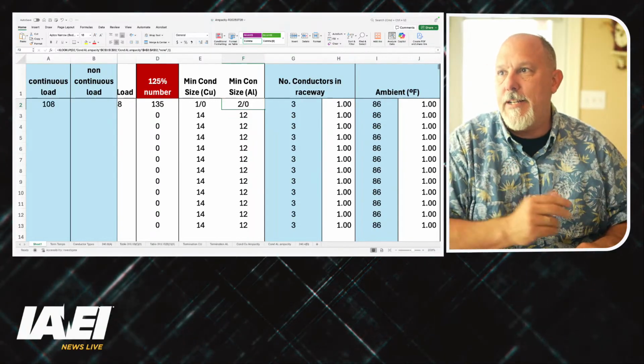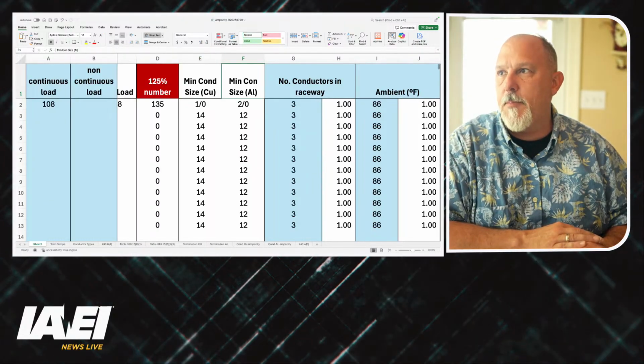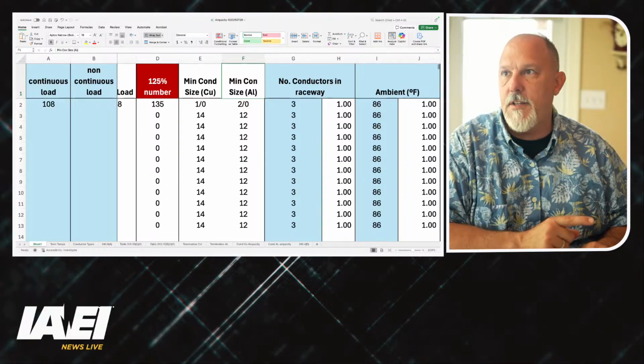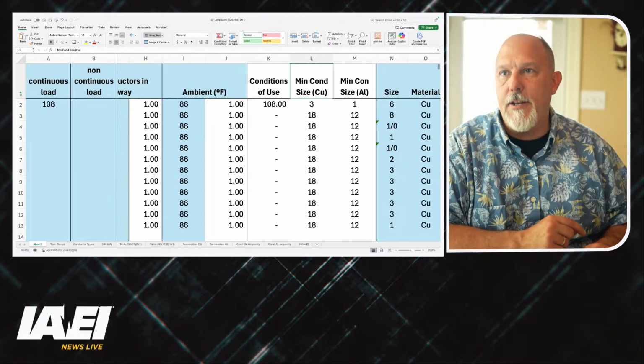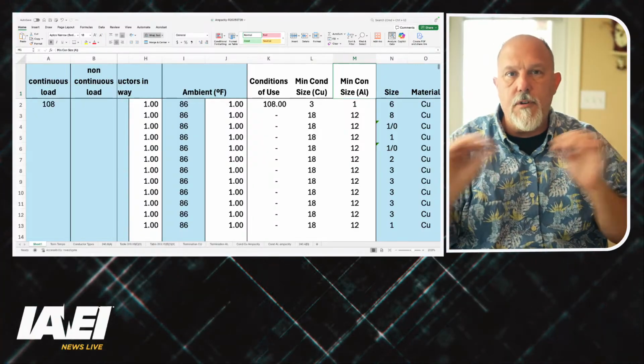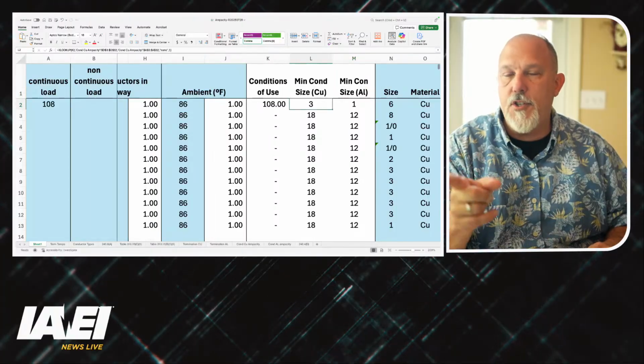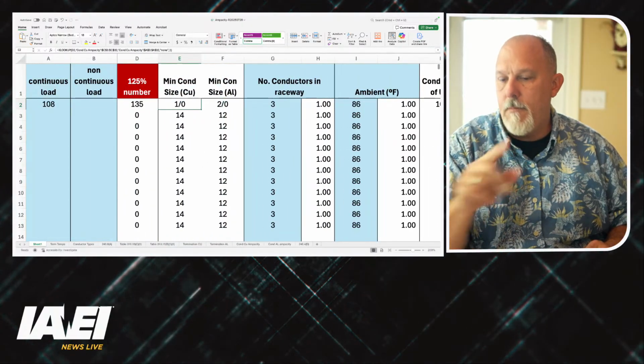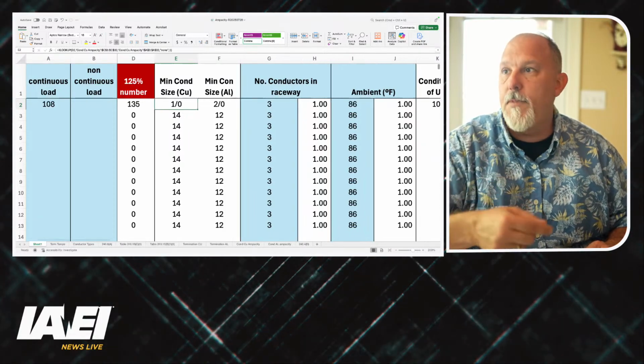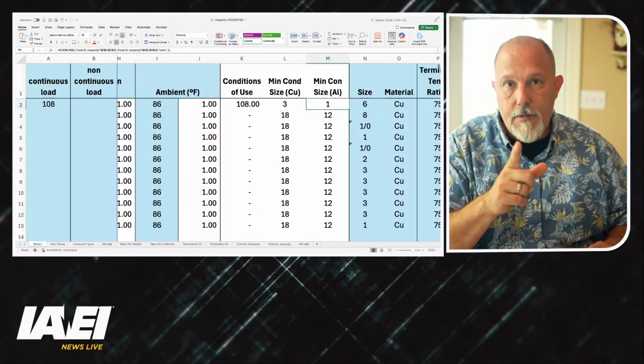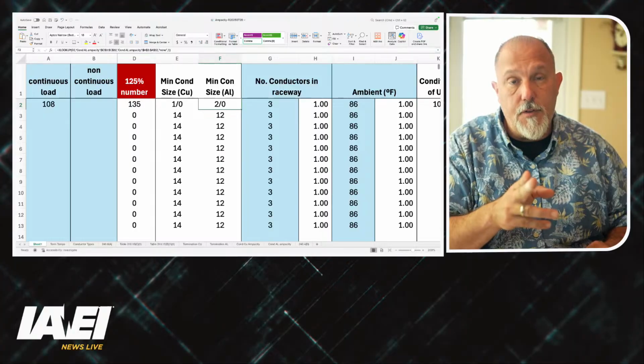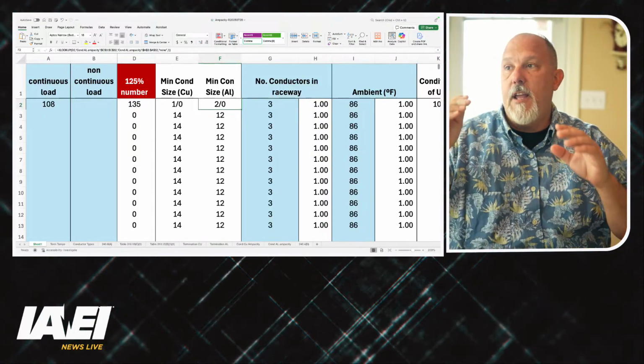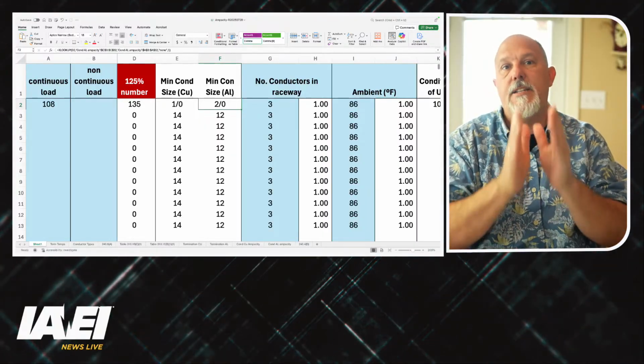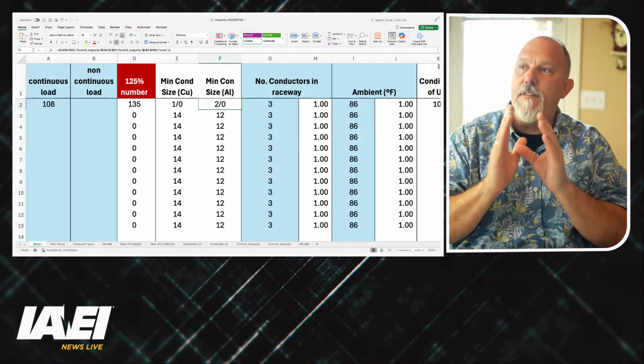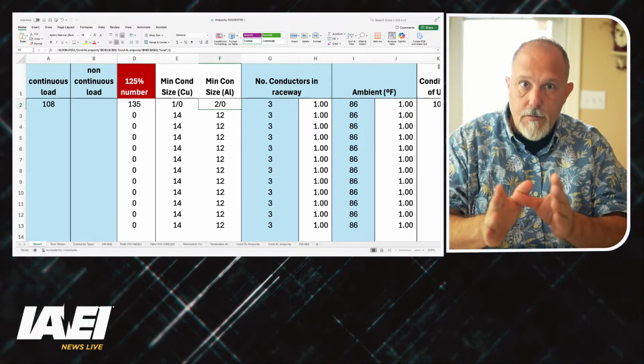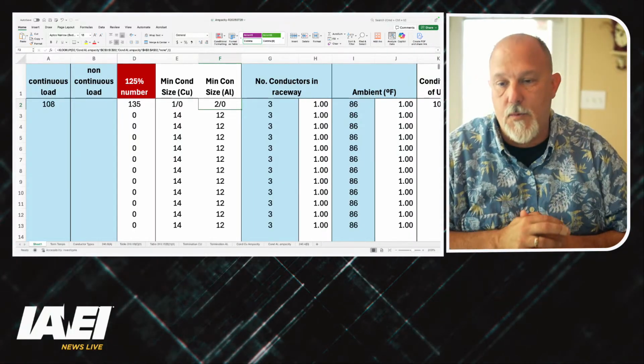You do the two calculations. I determined the minimum conductor size for copper and aluminum based upon 125% of the continuous plus the non-continuous. I determined the minimum size copper and aluminum based upon the ampacity. The larger of the two is the one I pick. For copper, the larger of the two between a 3 gauge and a 1-aught is the 1-aught. For aluminum, I have a 1 gauge or a 2-aught. The larger of the two is the 2-aught. So if I have an aluminum application, the minimum size conductor has to be a 2-aught. If I have a copper conductor installation, then my minimum size is a 1-aught.